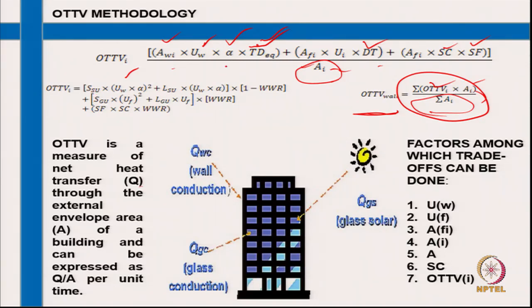Direct solar radiation will include the alpha value, so for that also you may have to calculate TD equivalent separately. So U of the wall is important, U of the fenestration is important, area of the fenestration is important, overall area is important, and the shading or solar coefficient, area — for each one you can find the OTTV value.